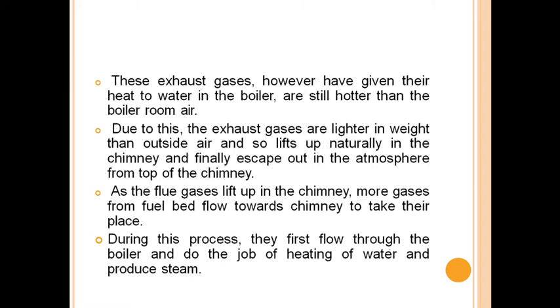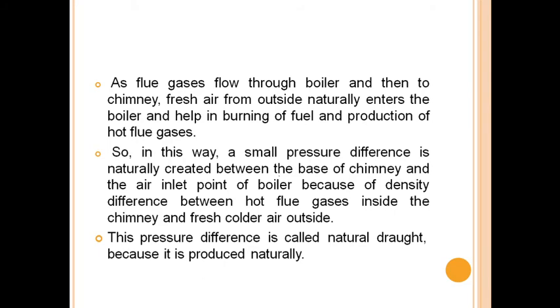During this process, the gases first flow through the boiler, performing the job of heating water and producing steam. As flue gases pass through the boiler and then to the chimney, fresh air from outside naturally enters the boiler and helps in burning the fuel and the production of hot flue gases. In this way, a small pressure difference is naturally created between the base of the chimney and the air inlet point of the boiler, because of the density difference between the hot flue gases inside the chimney and the fresh cold air outside. This pressure difference is called natural draught because it is produced naturally.